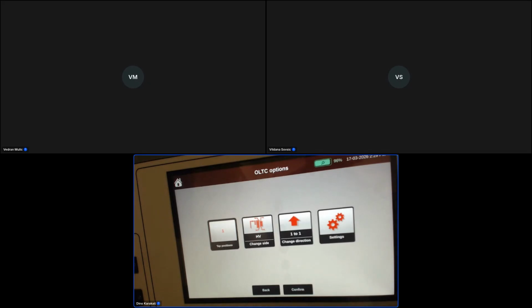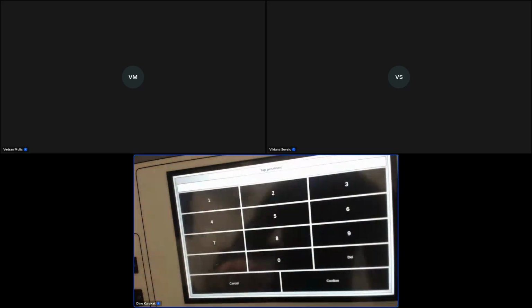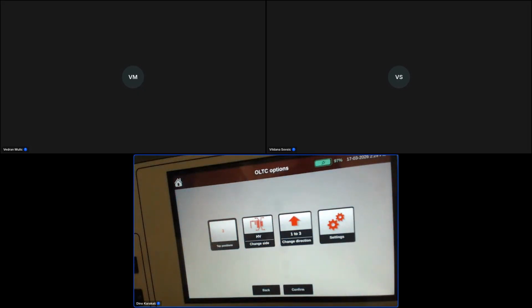It asks us how many tap positions there are. So we will say for this opportunity that there are 3 tap positions. Press confirm. Now the device wants to know if the tap changer is on the high voltage or low voltage side. We can toggle between these options, but it's on the high voltage side. We'll test from first to third, and we can press confirm.